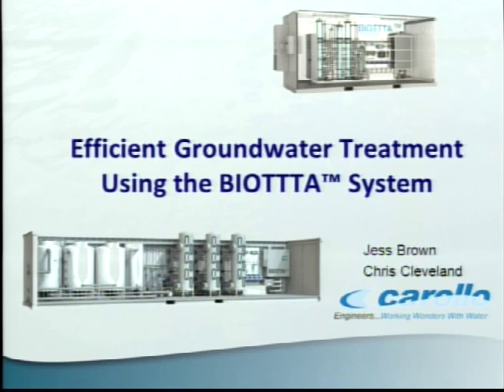Again, there's multiple reasons. You're right. It's not as cheap as just aerating, but it also gives you some advantages in certain scenarios. It keeps everything in line when you aerate the water. If there's anything that's volatile, hydrogen sulfide, VOCs, you have to worry about capturing that. We also use the hydrogen peroxide as a biomass control agent. Found it to be extremely effective. And if there's one thing I've learned in the last 15 years on this system, it's that with the hydraulics of a biological process, in particular a fixed bed process, you cannot put enough emphasis on maintaining good hydraulics with your backwash and whatever biomass control systems you have.